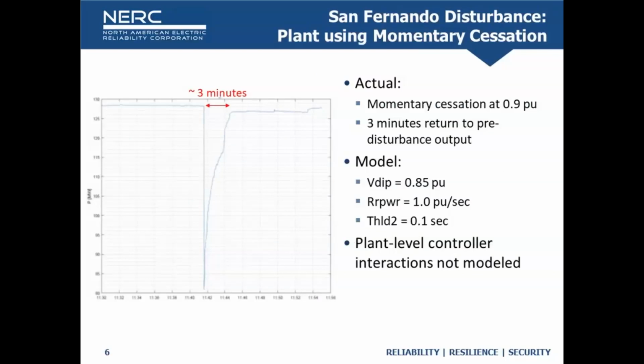When we look at the model, it shows a VDIP of 0.85 per unit, a rate of active power recovery of 1 per unit per second. So it should take a second for the resource to come back after momentary cessation occurs. And there's about 100 millisecond delay before the resource begins coming back after the voltage has recovered to acceptable conditions.